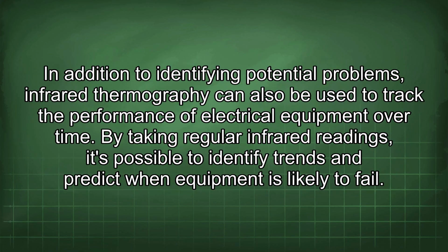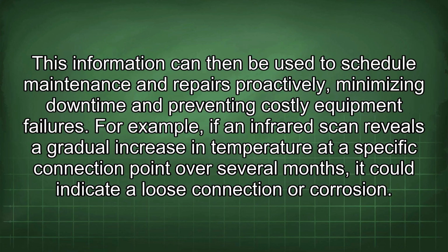In addition to identifying potential problems, infrared thermography can also be used to track the performance of electrical equipment over time. By taking regular infrared readings, it's possible to identify trends and predict when equipment is likely to fail. This information can then be used to schedule maintenance and repairs proactively, minimizing downtime and preventing costly equipment failures. For example, if an infrared scan reveals a gradual increase in temperature at a specific connection point over several months, it could indicate a loose connection or corrosion.